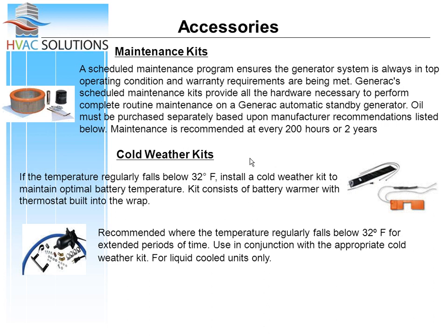Cold weather kits. Here in Chicago, I do not recommend them unless the application calls for it, and by that I mean the application is critical in some fashion. You know, somebody on life support, yeah, let's put in the cold weather kit. Or maybe somebody needs the stair lift to get from one floor to another. That's a critical application. And I don't generally offer them because it's an expensive kit. It's basically a crankcase heater. But this thing costs in the neighborhood of $250, and generators are pretty tight. So if you're offering it and the other guy isn't, you'll look that much further out of the ballpark.